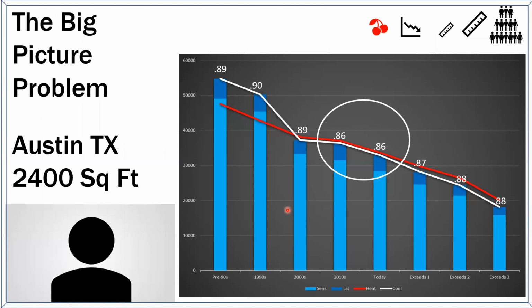If you ever get confused about which is which, here's how to remember it. When you make things cold, the temperature drops—that makes sense, right? That's sensible. You make things colder, temperature drops, that's sensible. Latent is the hidden energy use—latent means hidden. So you make things cold and some moisture comes out of the air; it doesn't affect the temperature, but you're still using that energy. That's the hidden energy being used to remove moisture.